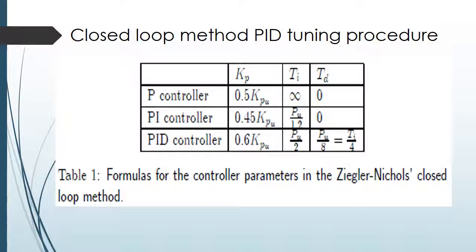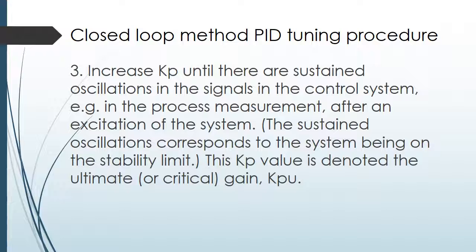For the PID controller: TD is PU over 8, which equals TI over 4. That completes Table 1 with the formulas for the controller parameters in the Ziegler-Nichols closed-loop method. For step three of the tuning procedure: increase KP until there are sustained oscillations in the signal in the control system — for example, in the process measurement after an excitation of the system. The sustained oscillation corresponds to the system being on the stability limit. This KP value is denoted the ultimate or critical gain, with symbol KPU.